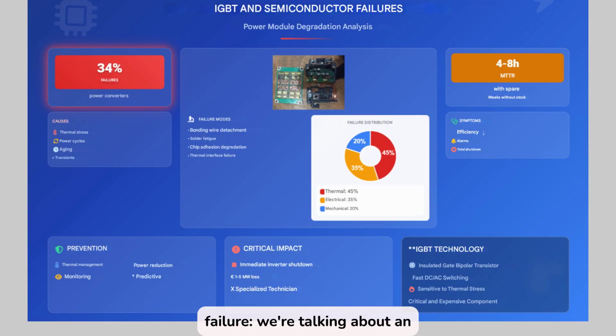We're talking about an essential component whose failure can cause the inverter to completely shut down, directly affecting energy production and project revenue. Their significance is such that, in many cases, these events are considered critical incidents that trigger emergency protocols. IGBT failures represent 34% of the total failures detected in utility-scale photovoltaic inverters, making them the most common type of failure in real-world environments.